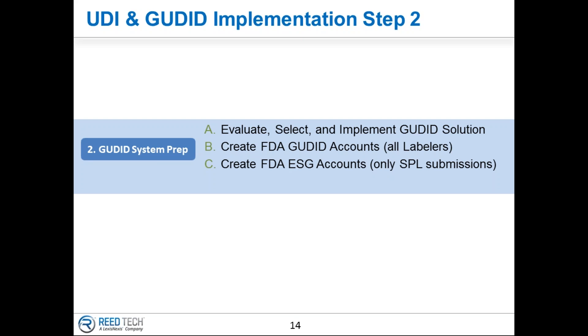Deborah asks: if a device has multiple components such as a power cord adapter, a controller, and a powered warming mattress that can be purchased separately or together, do each of the components need a separate UDI? The FDA has addressed this. If all those individual components are sent out as a system, the system needs a UDI. But if some components are sold and marketed on their own, then the FDA requires those individual components to have their own UDI separate from the system UDI.